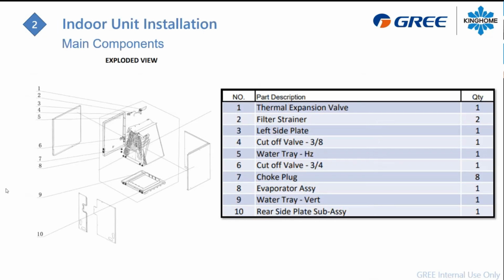So what's inside of that kind of case coil? Again, it will have 2 different pans, so you can flip the case coil. It can be a vertical or a horizontal installation. And inside of it, you will find a TXV, a thermal expansion valve. This valve will be managed from the pressure of the refrigerant and the temperature of the suction line, but it will not be electronic, it will be a thermal expansion valve.